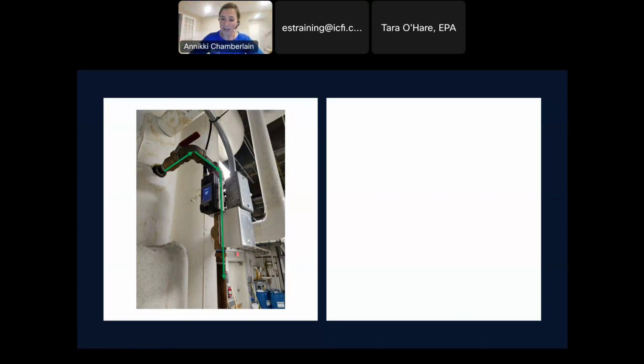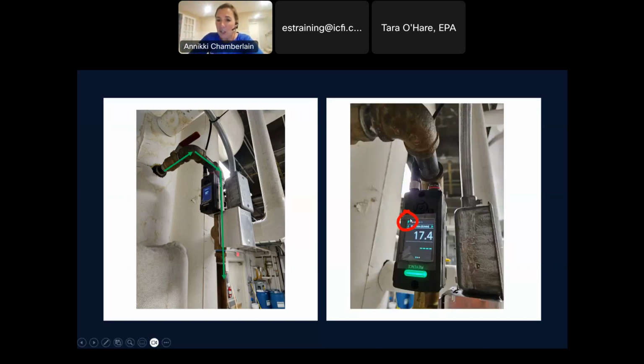I'm just going to try it. So clamp it in. Right here is a stability indicator, and that's going to say how stable the flow is, because what those clamp-on meters are looking for is basically laminar flow. You can't have a bunch of turbulence, because then that sound signal gets thrown off. The most bars you can have is 4, and this thing is running at 17 gallons a minute for the blowdown, and I got 4 stability bars. So boom, I am good.